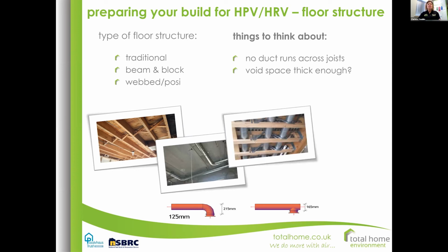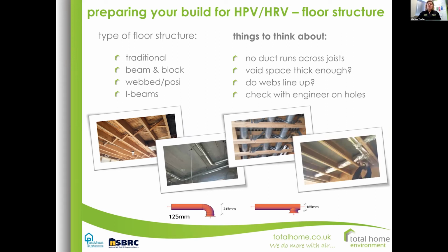Webbed or posi joists, good. You can go across. Just make sure that all the Ws actually line up, so that you don't have to cantilever the ductworks, otherwise it's a pointless exercise. And I-beams or engineered beams, these are good. You can run across them, but you do need to check with your engineer exactly how big the holes can be and exactly where in the beams they are allowed to be.